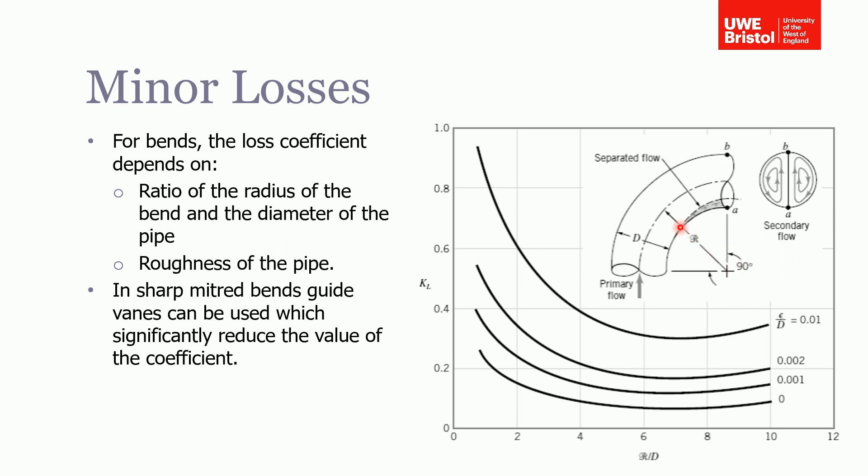Firstly, how tight the bend is—that's defined as the radius of the bend to the diameter of the pipe—and also on the roughness of the pipe. You can see here, for example, if we had a radius to diameter ratio of six and a relative roughness of 0.001...